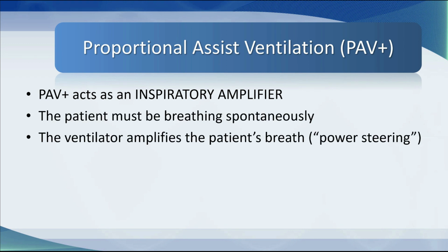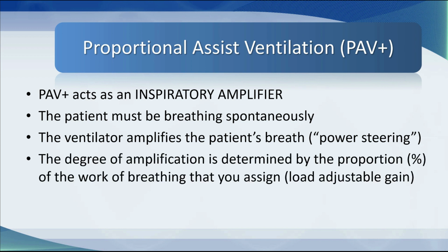The ventilator amplifies the patient's breath, and it's a bit like power steering for breathing. The degree of amplification is determined by the proportion of the work of breathing that you assign. It's load adjustable gain, and it works like the volume dial in a music system. You dial upwards to increase the gain, to increase the volume, and you dial downwards to reduce the gain or reduce the volume.